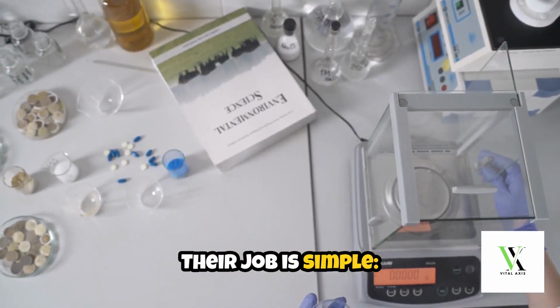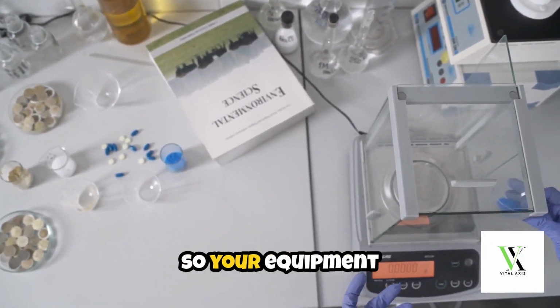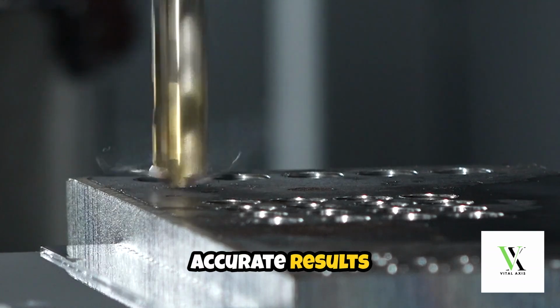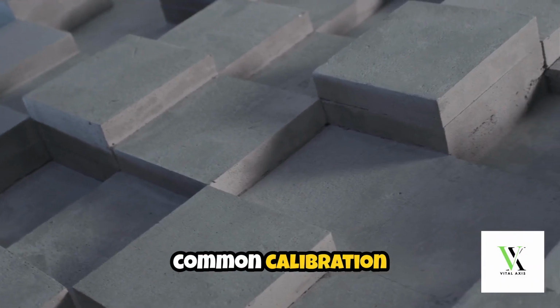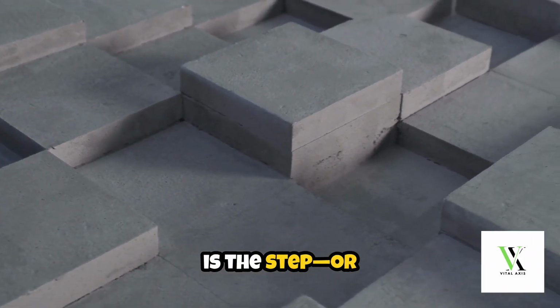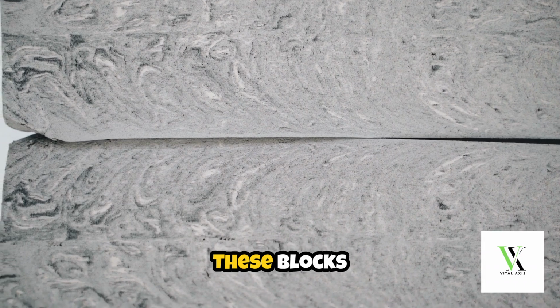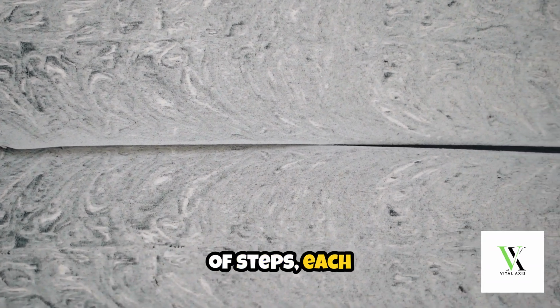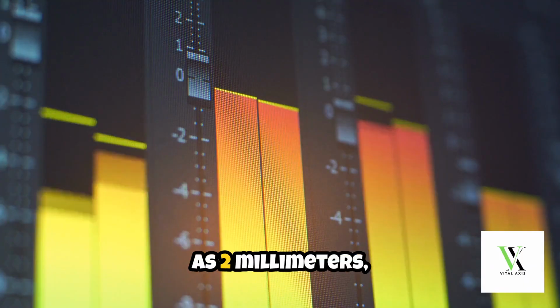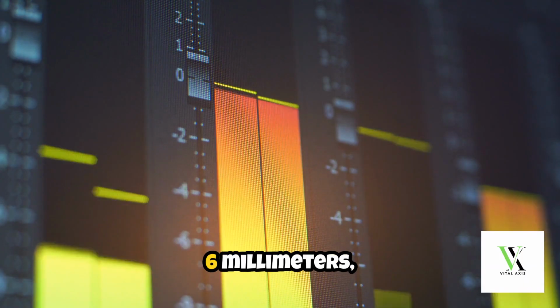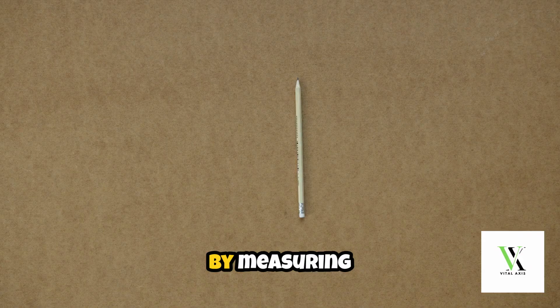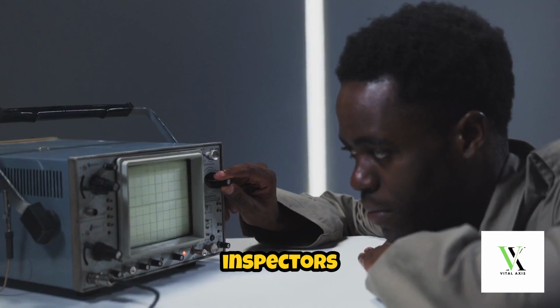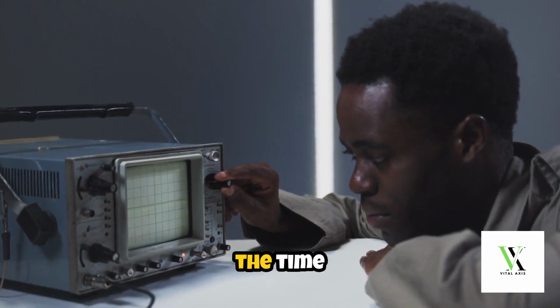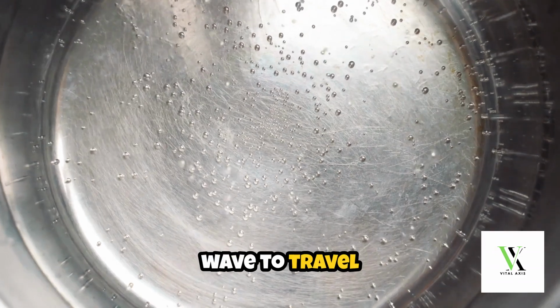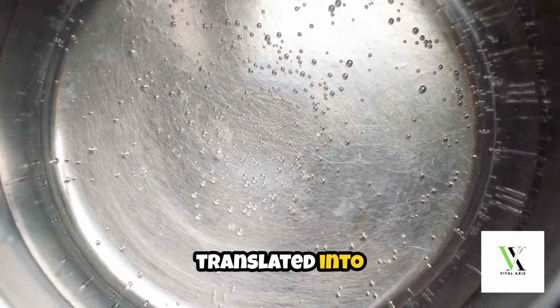Their job is simple: provide a known reference so your equipment can be tuned to deliver accurate results in the field. One of the most common calibration tools is the step, or wedge, block. These blocks feature a series of steps, each with a known thickness, such as 2 mm, 4 mm, 6 mm, and so on. By measuring each step and comparing the readings to the known dimensions, inspectors calibrate their gauges, ensuring the time it takes for a sound wave to travel through steel is correctly translated into a thickness.